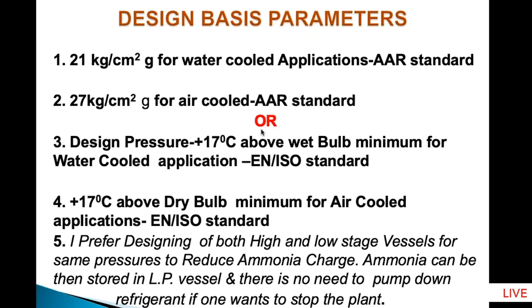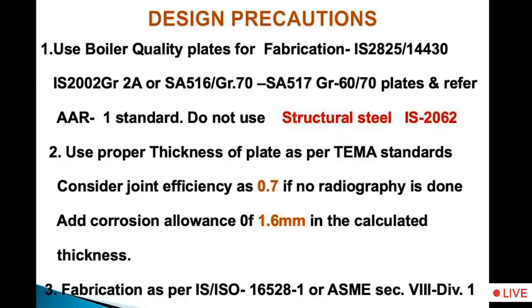This is my comment, fifth one. I would prefer designing both high side and low side vessels for the same pressures. This will allow you to reduce ammonia charge. Ammonia can then be stored in the LP vessel in the plant room, and you need not pump down the system. The next is design precautions.